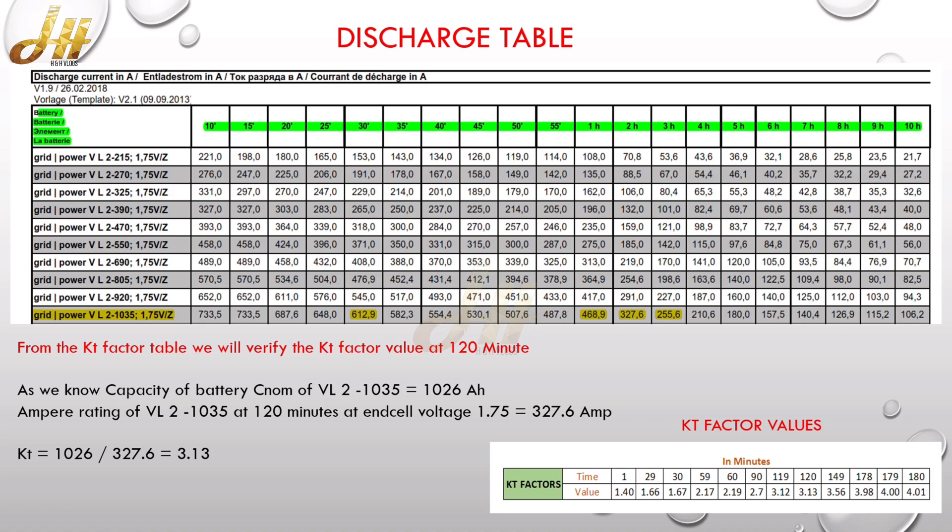For 120th minute, the KT factor value of the particular cell is 3.13. So now we will check how this can be derived. So you can see that nominal capacity of this battery is 1026 Ah, and from the discharge table on 120 minutes, which is the two hour, the discharge capability of that battery is 327.6 ampere.